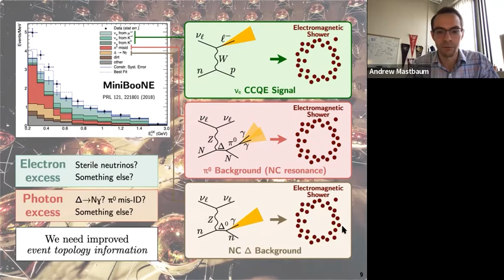kind of why we have chosen to adopt a different detector technology, the liquid argon time projection chamber. It's kind of a next generation detector type for neutrino experiments, where we get a few benefits. So we have now detailed 3D imaging of neutrino interactions at the millimeter spatial scales, calorimetric reconstruction of energy deposited in the detector, and very importantly for this particular search, the ability to discriminate between electrons and photons with a few different handles using vertex displacement and calorimetry using the charge deposited per unit distance. So before I get into that, maybe just a quick sketch of how these detectors work. I have a cartoon here at the bottom of a liquid argon TPC.